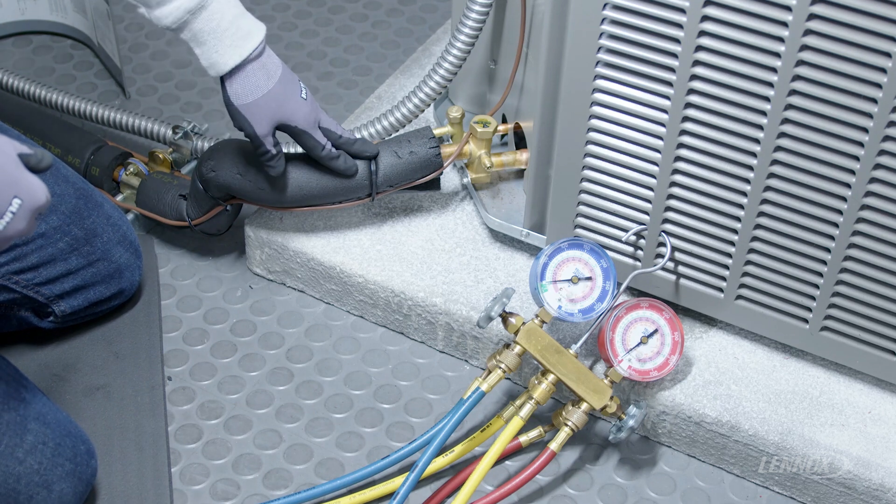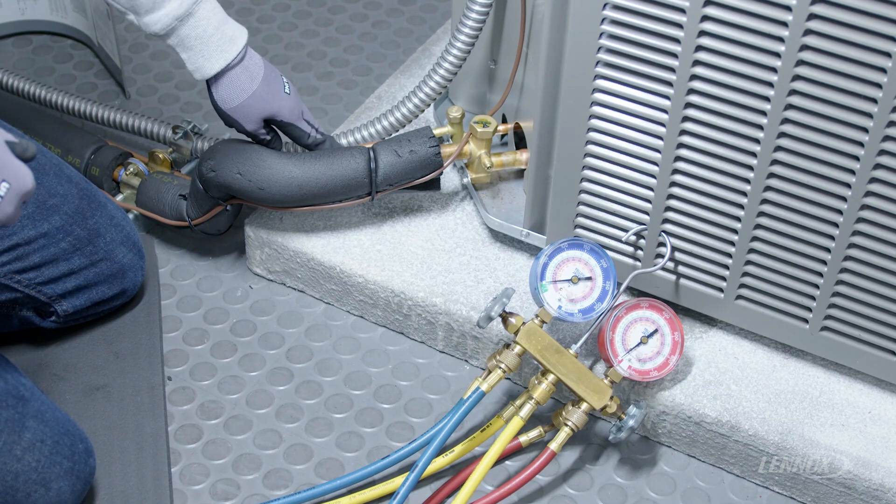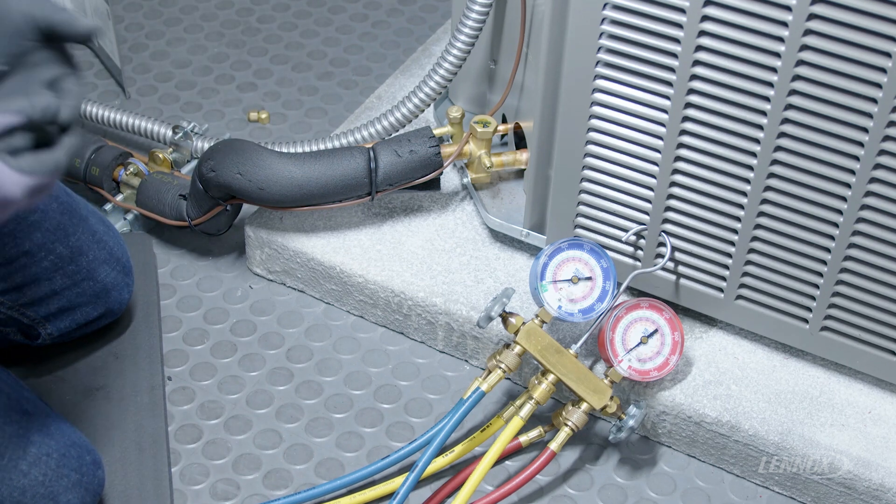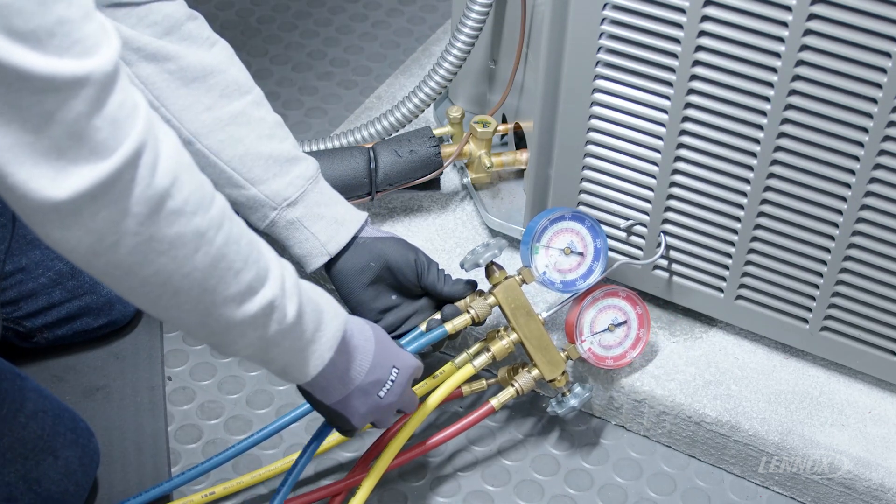Respectively, our suction line is cold and typically in an air conditioner, our liquid line is warm. So in terms of which gauge to hook up, think blue for low side and red for high side.